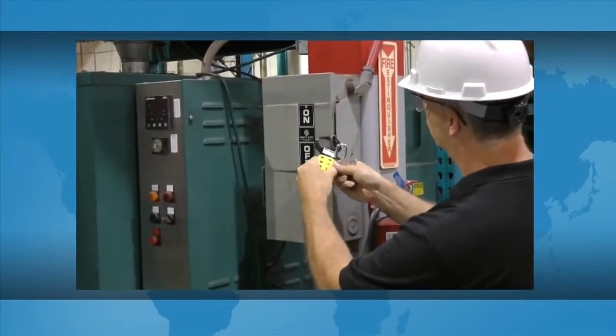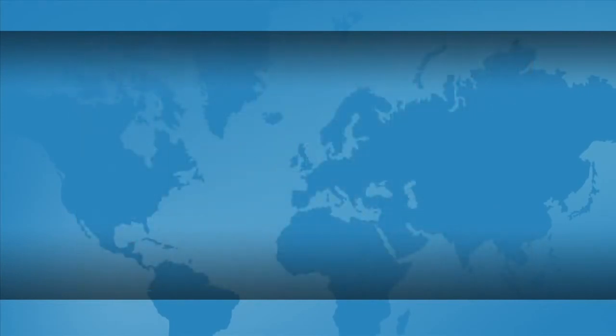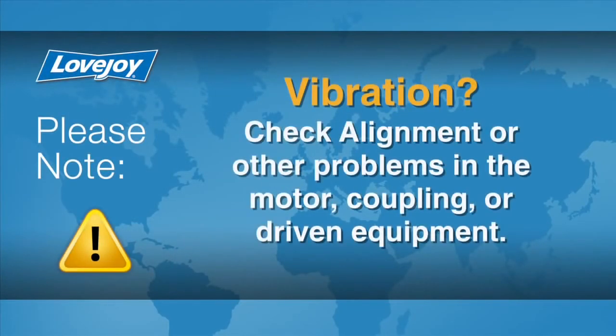The equipment can then be started up and tested. The coupling and equipment should run smoothly. If vibration is detected, it could indicate that there is an issue with alignment or other problems. These could exist in the motor, coupling, or driven equipment, and should be resolved prior to placing this coupling into operation.